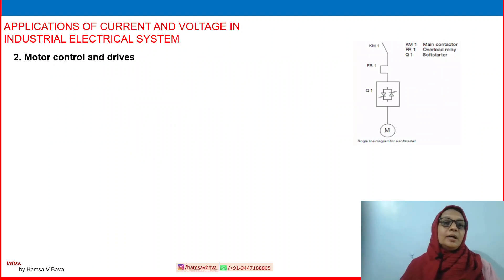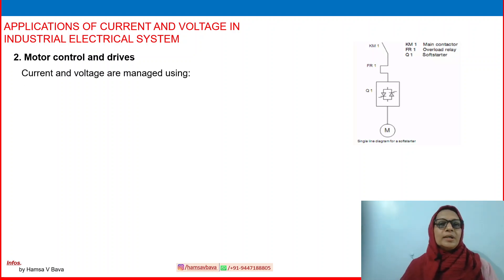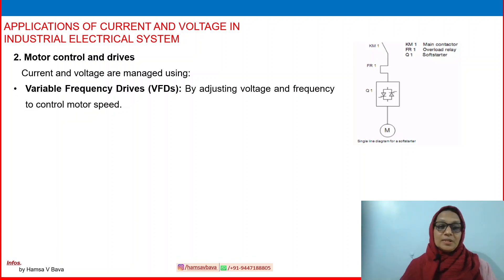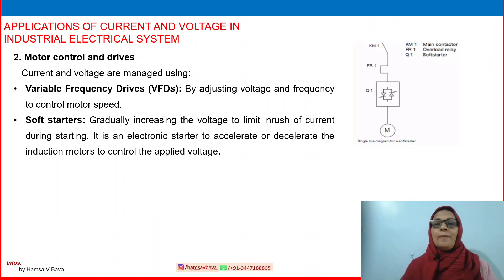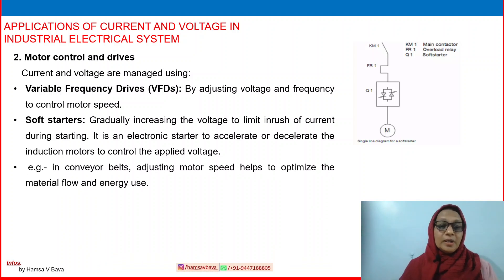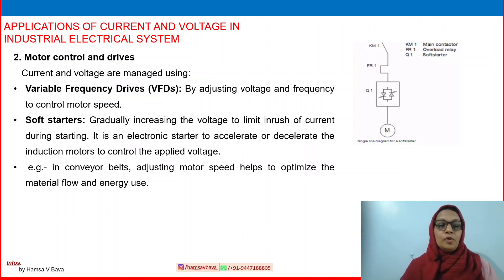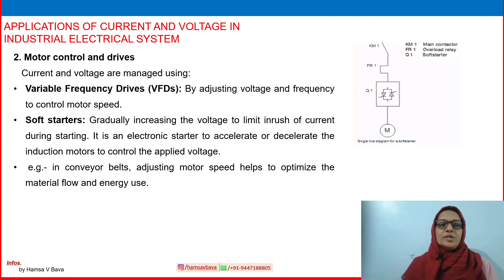Motor control and drives: motors are a crucial component in all industries. Current and voltage are managed using variable frequency drives, which adjust voltage and frequency to control motor speed. Soft starters gradually increase the voltage to limit the inrush of current during starting — they are electronic starters used to accelerate or decelerate induction motors by controlling the applied voltage. In conveyor belts, adjusting motor speed helps optimize material flow and energy use, controlled by the soft starter.